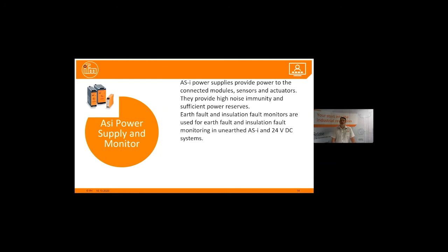The ASI power supply provides power to the connected modules, sensors, and actuators. They provide high noise immunity and sufficient power reserves. Earth fault and insulation fault monitoring are used for earth faults and insulation faults in unearthed ASI and 24-volt DC systems. In short, when there's a problem on a circuit, I can identify it, especially on the data side as well as on the power side.